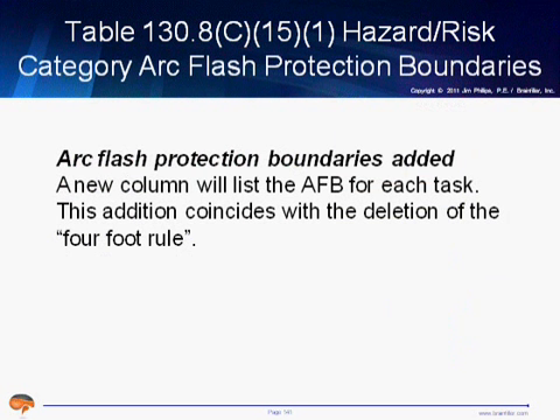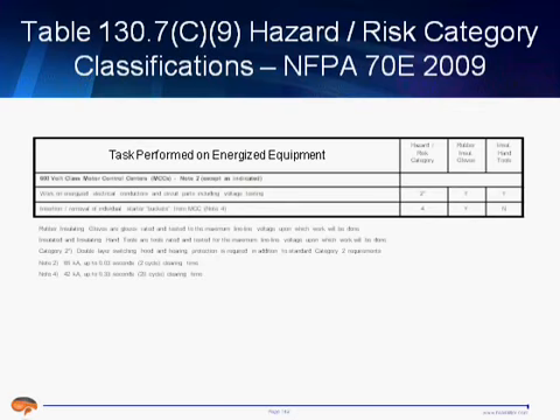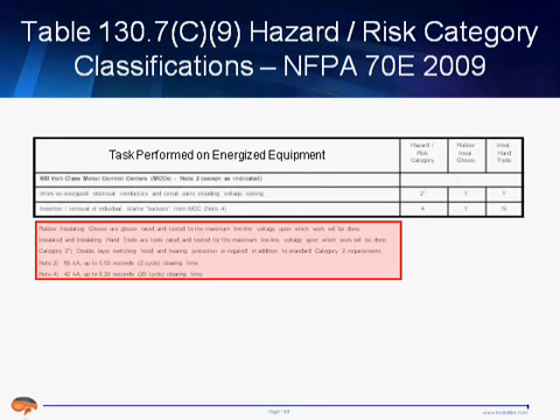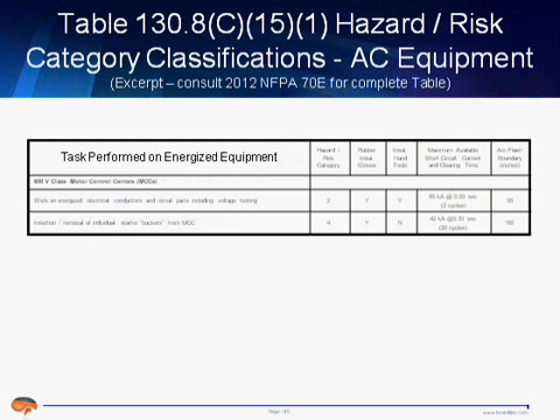The hazard risk category boundaries, or excuse me, the hazard risk protection boundaries, these are going to be included in the tables. Back in 2009, these are the 2009 tables that I have up right now. You would look up the equipment, you would look up the task, and then you would have to know to follow the limitations of the footnotes. Well, beginning with 2012, a lot of the good information from the footnotes is going to be included into the tables.